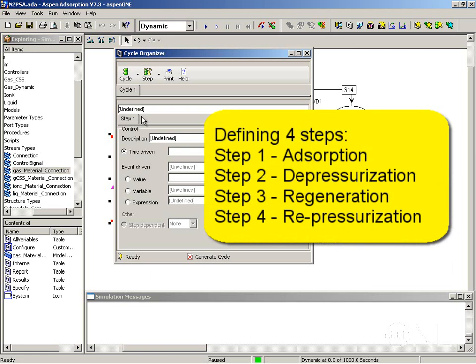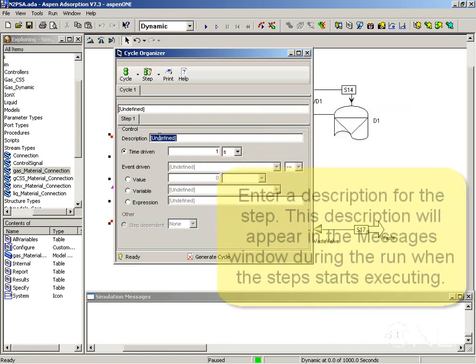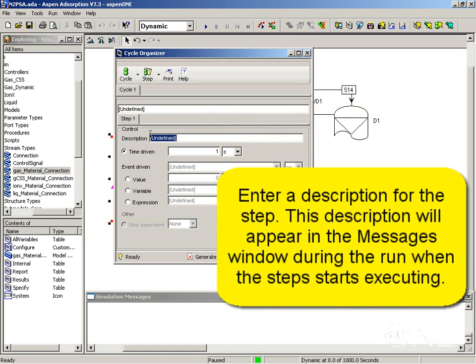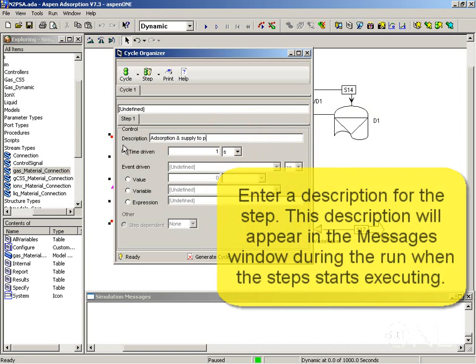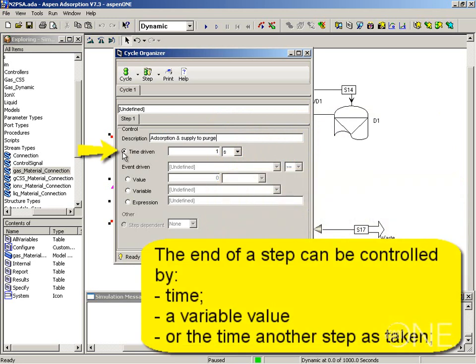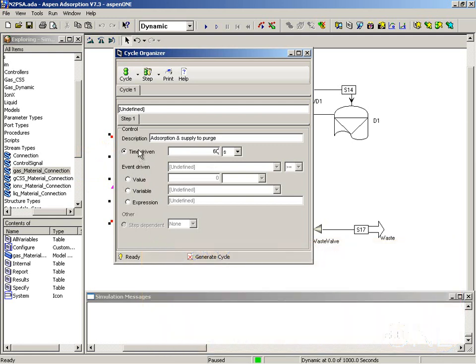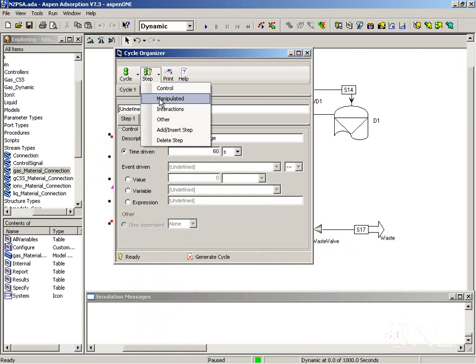Adsorption, depressurization, repressurization and desorption. So for step number one, we should give a description and this is going to be a time-driven step taking 60 seconds. We can also have an event-driven step where we compare values for variables but more commonly, we use an explicit end time for the steps. So now that we have defined the way the step is going to finish, we are going to add manipulated variables to it.